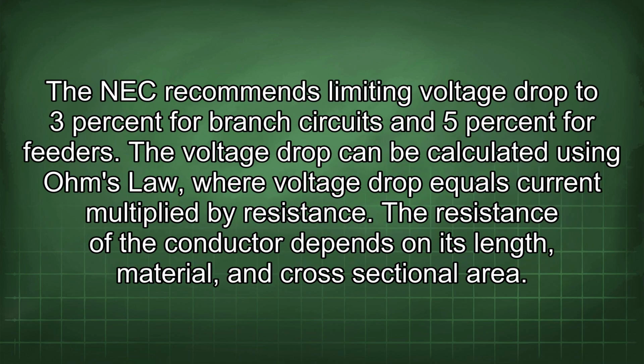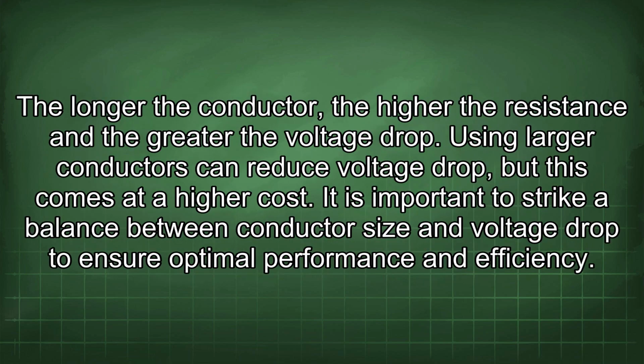The NEC recommends limiting voltage drop to 3% for branch circuits and 5% for feeders. The voltage drop can be calculated using Ohm's law, where voltage drop equals current multiplied by resistance. The resistance of the conductor depends on its length, material, and cross-sectional area. The longer the conductor, the higher the resistance and the greater the voltage drop.